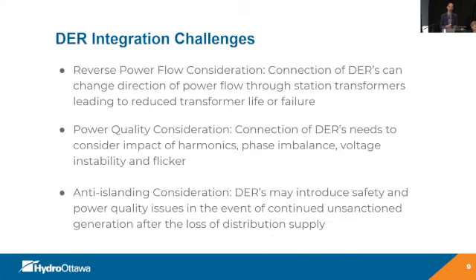There's reverse power flow considerations. As we connect DERs, traditionally, we have energy flow from the utility side going to the customer. Now we're going from the customer with a generator flowing back onto the grid. Not all of our equipment is designed and able to accommodate the reverse flow. It can cause circulating currents that then reduce the life of the transformer or, again, cause failure of that equipment.